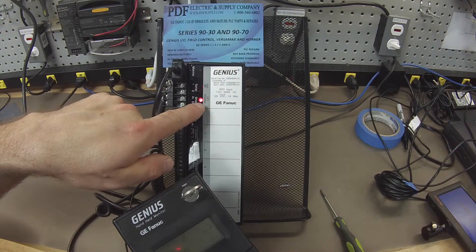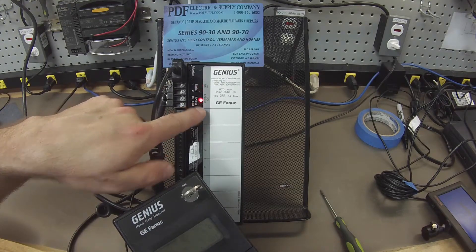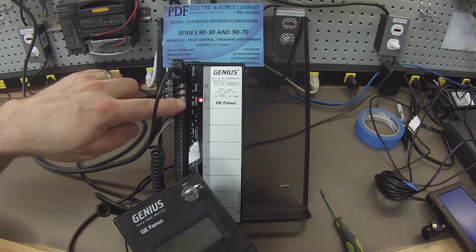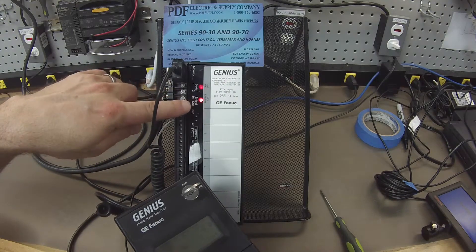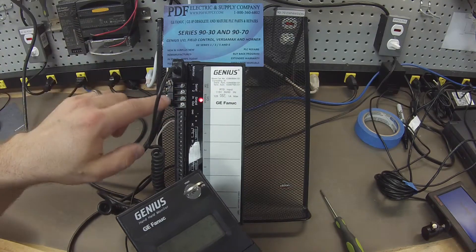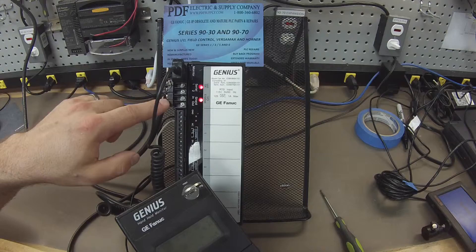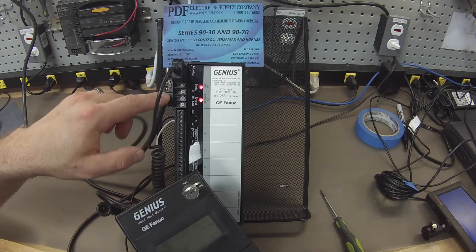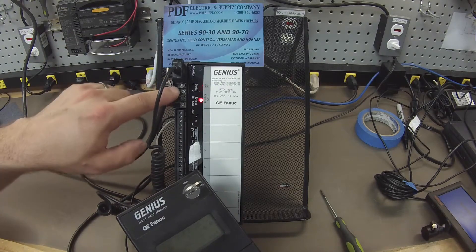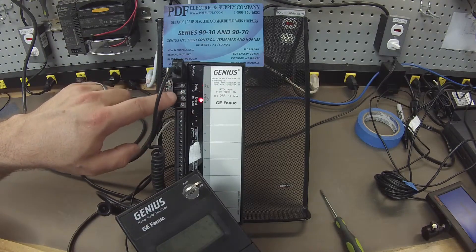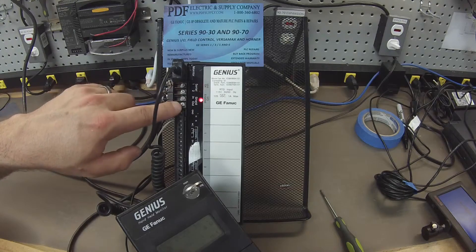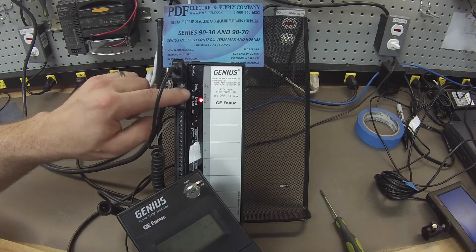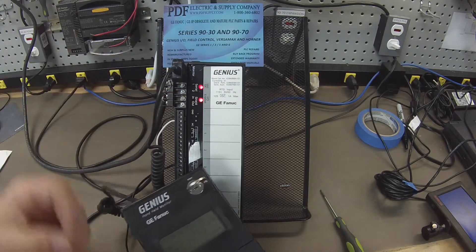light. And that tells me now that this Genius Block is communicating or talking with the bus controller and also the CPU through the serial port. So now I'm testing the serial port to make sure that that's working and it is.